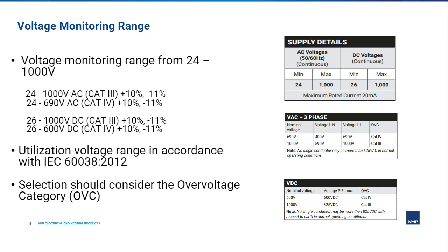Now, despite the wide voltage range that the unit can monitor, for where the unit will be installed in the distribution system, it's important to consider the overvoltage category, as this influences the monitoring voltage specification of the REMLIVE unit. As you can see on the slide, for overvoltage category 3 applications, the monitoring voltage range specification is 24 to 1000 volts AC and 26 to 1000 volts DC. This is whereas for Cat 4 applications, the monitoring voltage range specification is 24 to 690 volts AC and 26 to 600 volts DC. I'll go into more detail about overvoltage categories in the upcoming slide and why this should be considered as part of component equipment selection for an application.